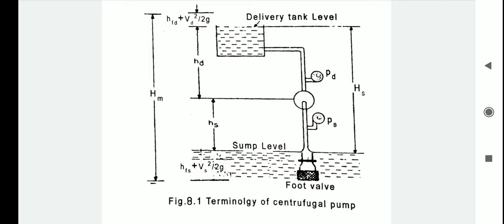In other words, the actual head against which the pump works is known as manometric head, HM. It is therefore in general equal to Euler's head minus the various hydraulic losses. By applying Bernoulli's equation between the sump and the delivery tank level, HM equals (PD minus PS) / ρg, which equals HS plus HD plus HFS plus HFD plus Vd² / 2g, which also equals HC minus (Vs² minus Vd²) / 2g. Here HFS and HFD are the frictional losses due to friction in the suction and delivery pipes respectively.